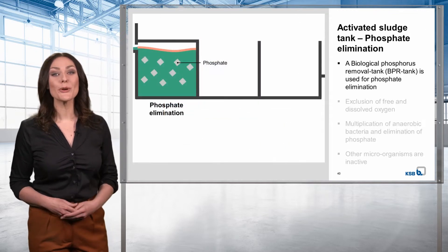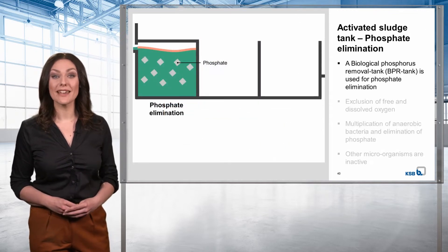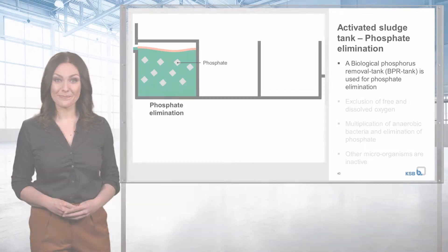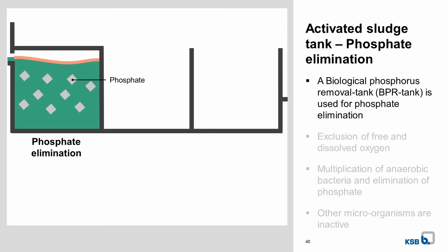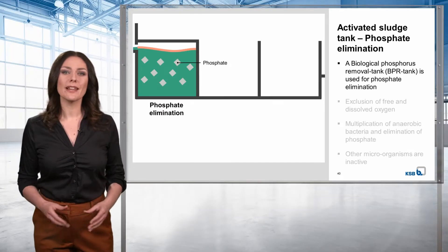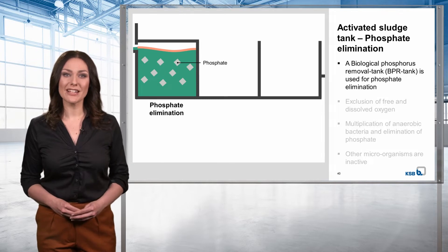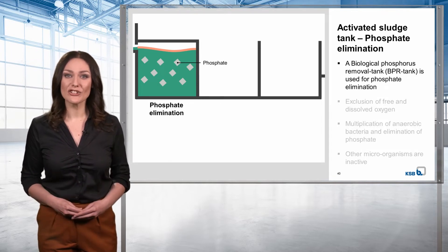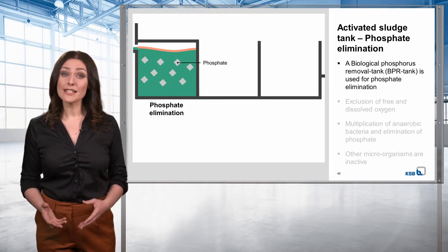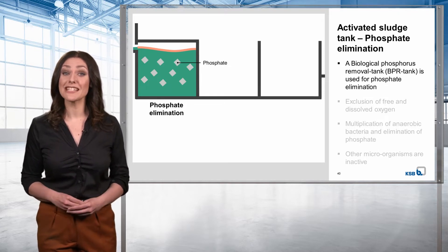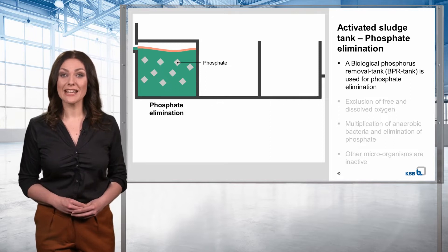Here in Huller, a so-called BPR tank is used for phosphate elimination. BPR stands for Biological Phosphorus Removal, sometimes also called a Bio-P tank. Not all plants use a separate phosphate elimination stage, as this process can also take place naturally. The trend is for modern plants to increasingly use phosphate precipitation instead of elimination.